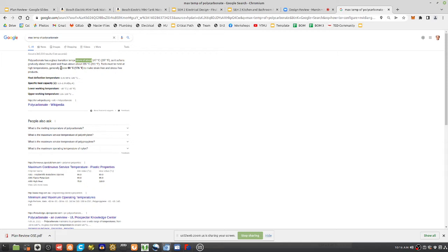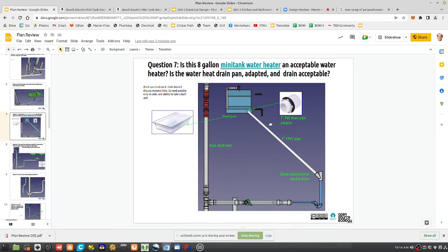Yeah, it should be. So what is that pressure relief valve preset? What's the pressure? Oh, it's standard. If it goes above boiling, it's a pressure temperature relief valve. A standard on any heater. Okay. You bring up a good point. I don't think I've ever seen a drain pan that had CPVC fittings in it. That's PVC. So maybe they're thinking that when this thing discharges, a lot of it is going to go up into the atmosphere as steam. The water that does hit the pan, maybe they think by the time it gets to the drain, it's going to have cooled down enough that the PVC will stand it.